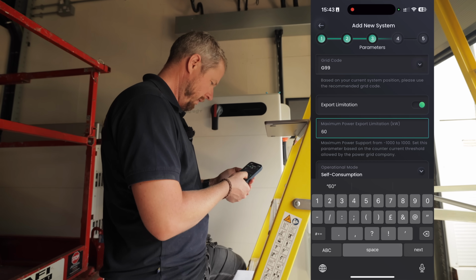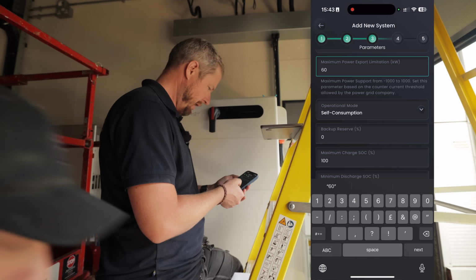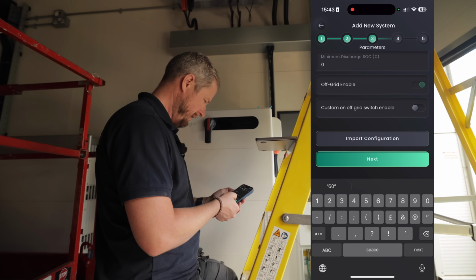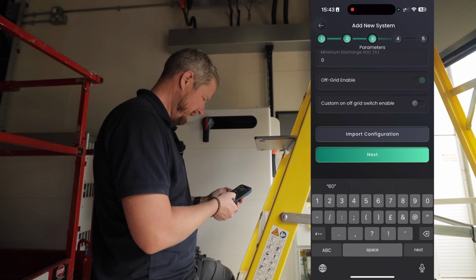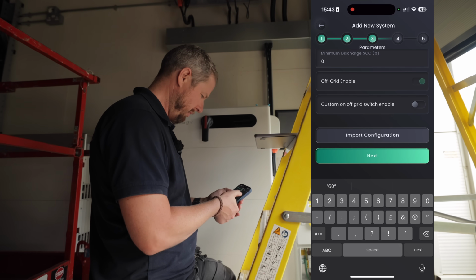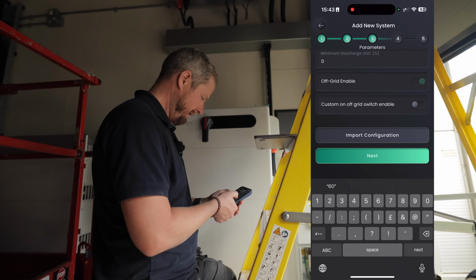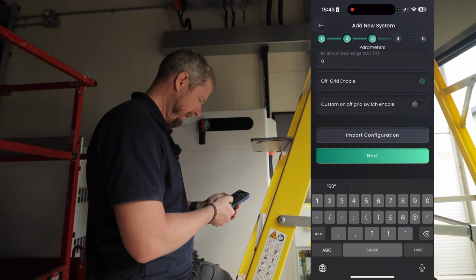All right, so we've got a 60 kilowatt export limit. Operational mode, self-consumption for the moment. Maximum charge, discharge, 0. Off-grid enable, on. Custom off-grid switch enable, we'll leave that for the moment.